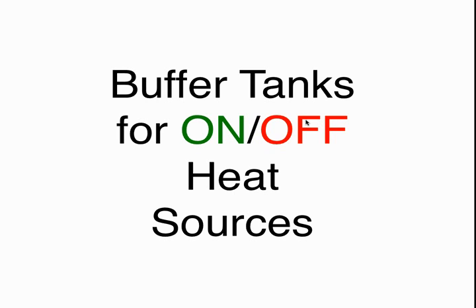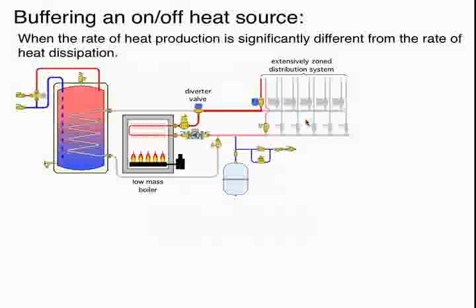Let's talk about buffer tanks now for on-off heat sources. So these could include boilers such as an oil-fired boiler or perhaps a dry-based gas-fired boiler, a heat pump, non-modulating heat pump. All right. So let's take a scenario.